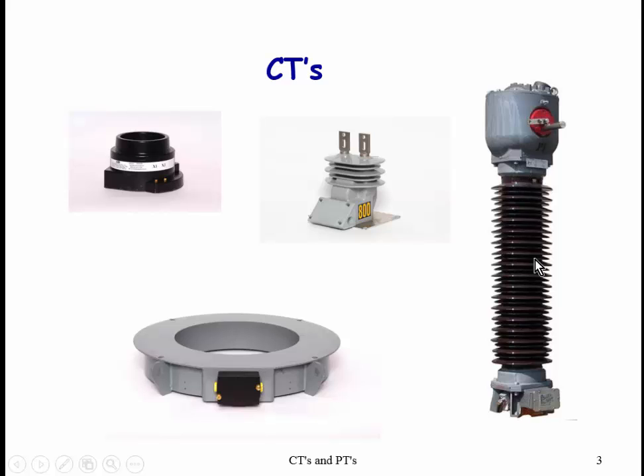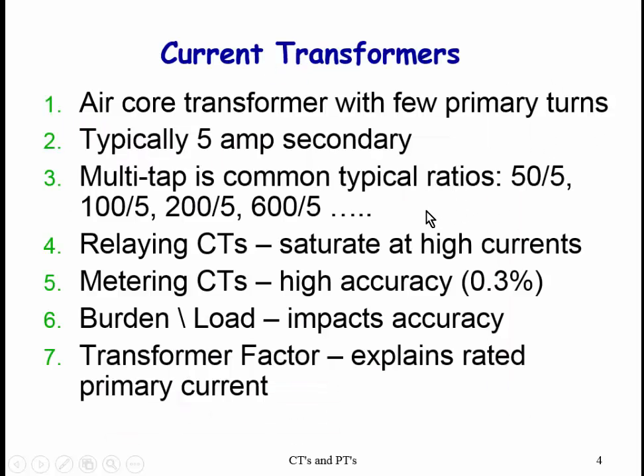This is basically the insulator, if you will, and then the CT goes through the top there. So what are they? Well, it's an air core transformer with few primary turns, usually one primary turn. The primary turn is the conductor that you've inserted through the middle of it. And we usually see these rated 50 to 5, 100 to 5, 200 to 5, that sort of thing, 400 to 5. Now, if you look at that, the ratio means this would be a 10 to 1 transformer, and this would be a 40 to 1 transformer.